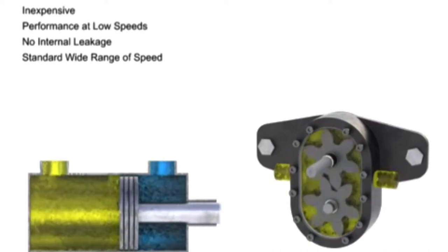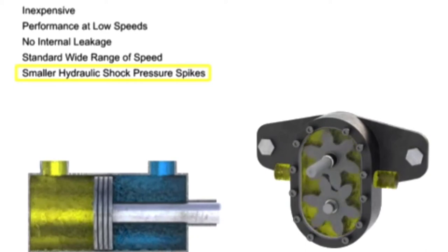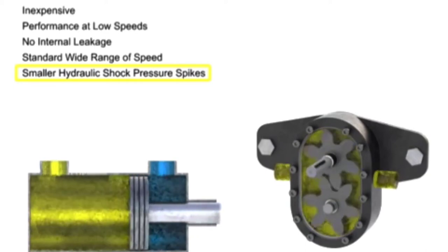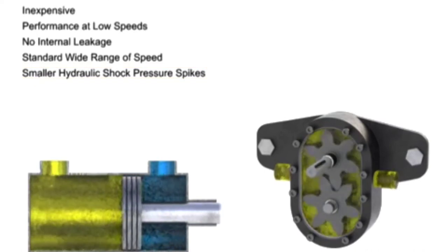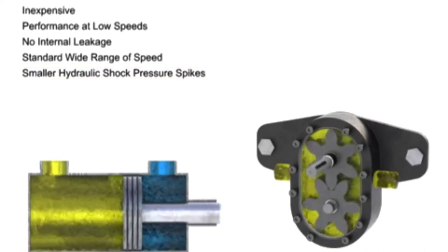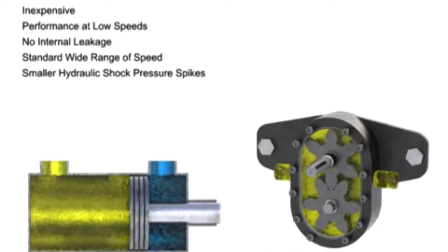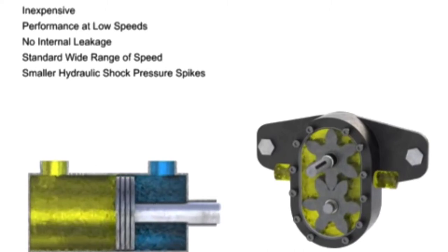Cylinders also produce smaller pressure spikes, called hydraulic shock, when stopped suddenly. Fluid motors tend to produce a much larger amount of hydraulic shock if stopped suddenly, due to the momentum energy contained in their rapidly rotating loads.